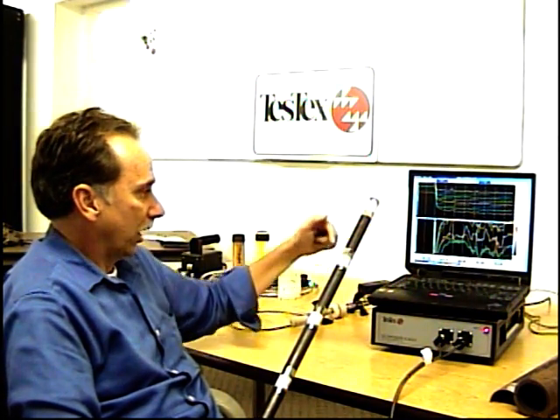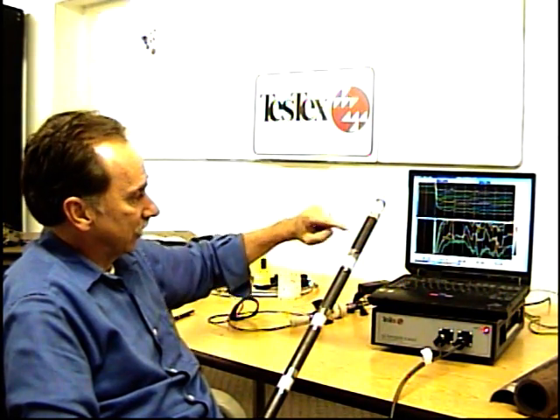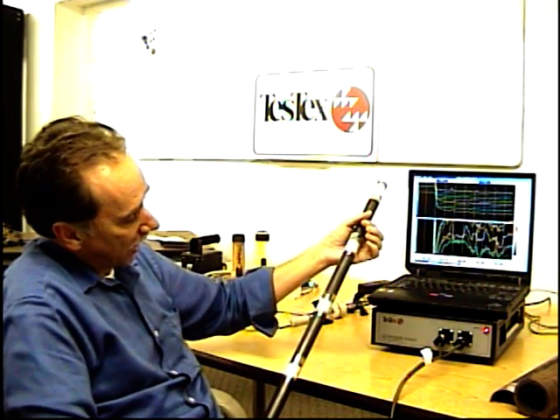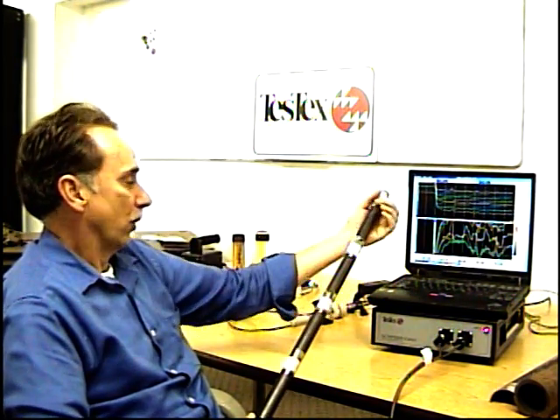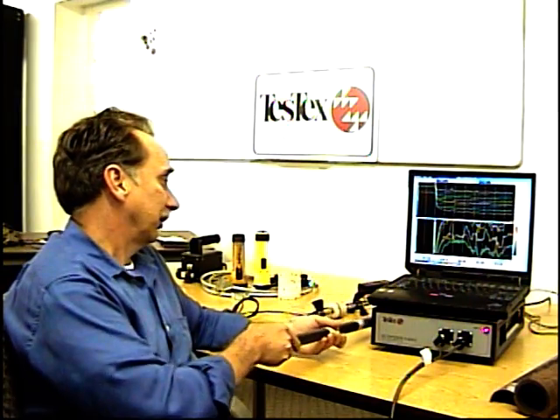With the multi-channel, it's not taking an average. Each sensor is dedicated to each part of the tube. So as it's sliding down the length of the tube, it's giving you an accurate reading with no averaging for the whole length of the tube. So that's one of the things you want to keep in mind when you're doing that.